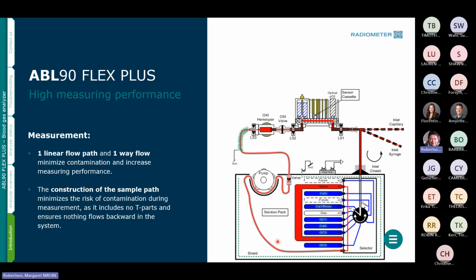I always like to show this picture because it gives you a chance to look at basically what the wet section looks like on the analyzer. And then this looks like where the cassette goes through. So you can see that the sample comes through here, goes straight in through the cassette, over here to the oxy module, and comes down in here and goes down through and into the waste container at the bottom. Inside here, it has 3 different levels of discrete packaged quality control material, and they're stacked in that solution pack. And again, you'll see that a little bit later when we actually go through the solution pack itself.